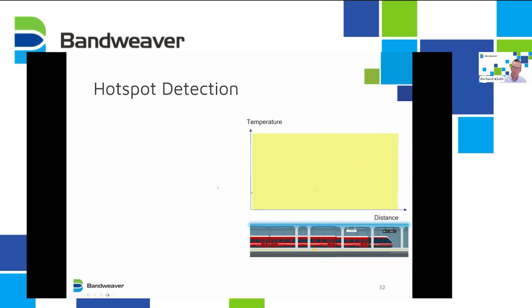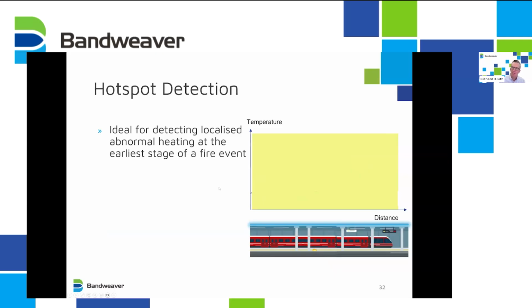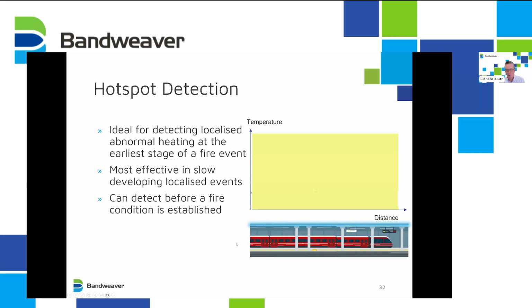The final alarm, hotspot detection. This is at the earliest stage, where the events can be slow and quite localized, where neither of the other two alarms may detect it. This has in a number of cases been the first to detect, again before a fire condition is established, and it's immune to ambient environmental changes.